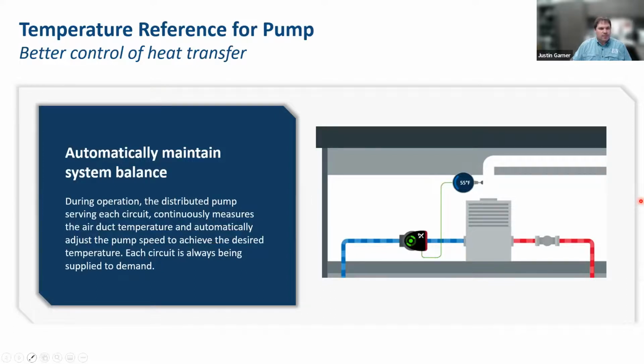And the balancer should be one of the folks on the project team that's going to verify that this pumping piece of the system is working correctly. It's taking the signal from the BAS or from an independent sensor, and it's modulating appropriately so that it can be ready for functional testing or whatever it may be as part of the commissioning process. So the short answer there is you still need the balancer even with this system.